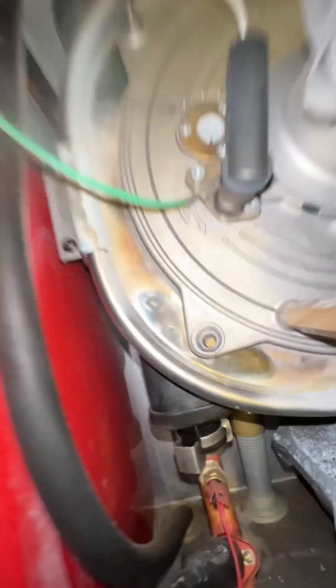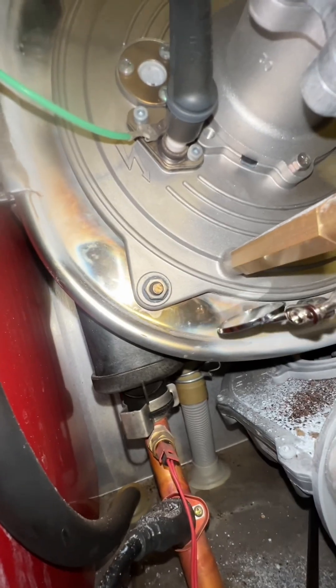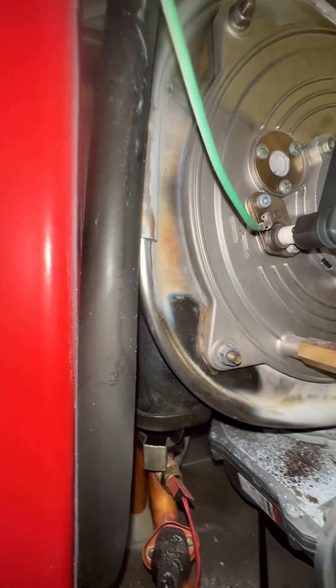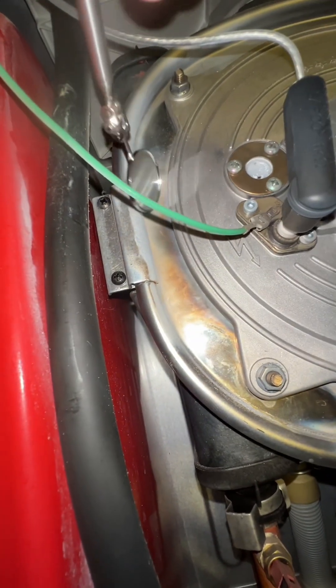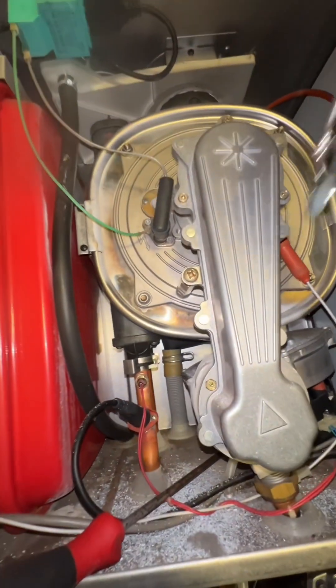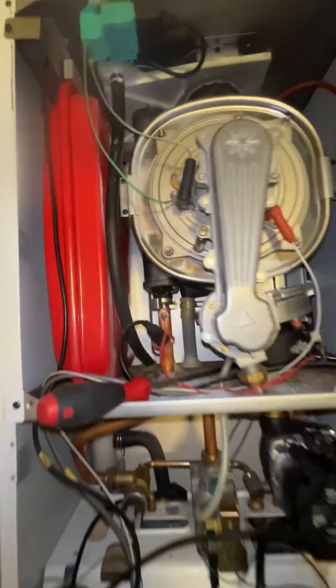On this boiler here you can clearly see products of combustion have been escaping through here — you can see the discoloration there. The seal has totally gone, and when I put my inspection mirror here it goes misty, which confirms it. So we're going to pull this apart now and change the seal around here. The seal is perished.